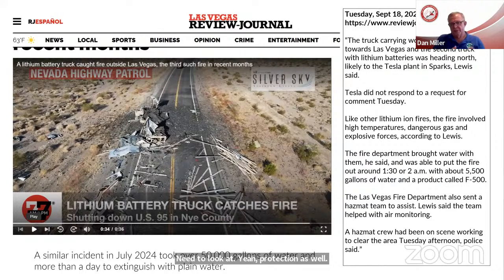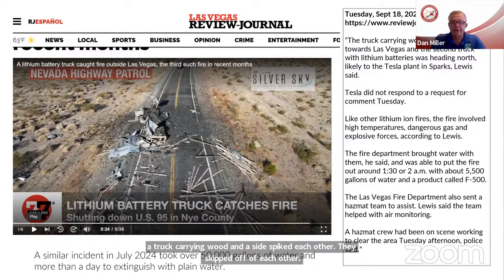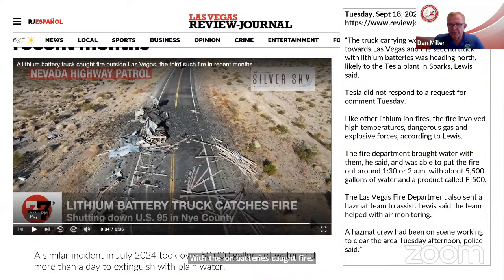So this incident we mentioned earlier: Tuesday morning, really early, a truck carrying lithium-ion batteries met a truck carrying wood, and they sideswiped each other. The lithium-ion batteries caught fire. The fire department brought F500, used about 5,500 gallons of water with F500 water additive, and were able to put the fire out very quickly. As opposed to the incident in July 2024 in Nevada, which took over 50,000 gallons of plain water and took days, this one took a very short period of time.